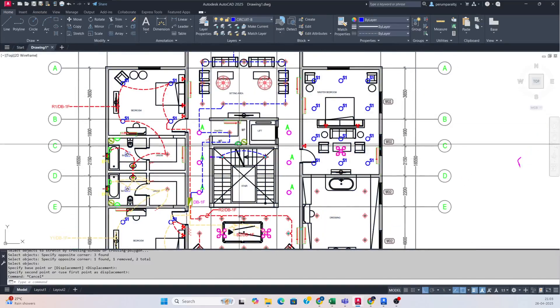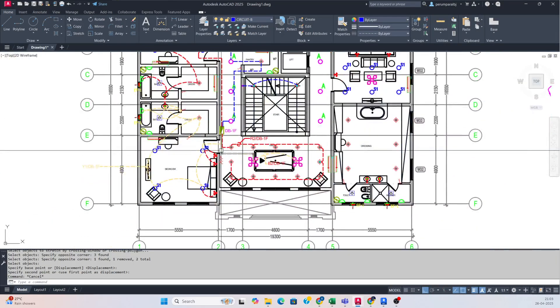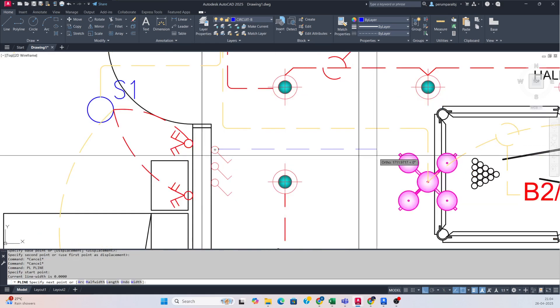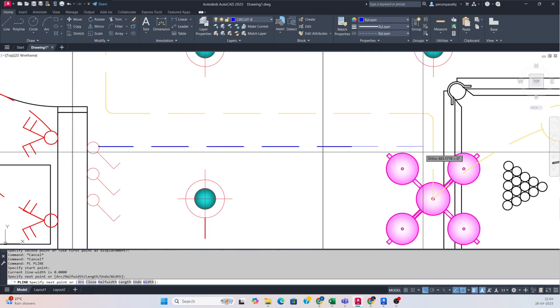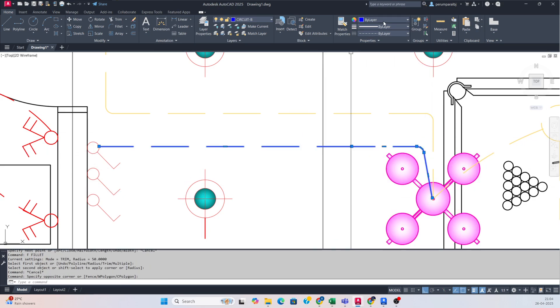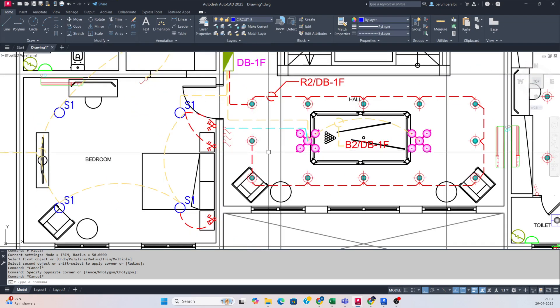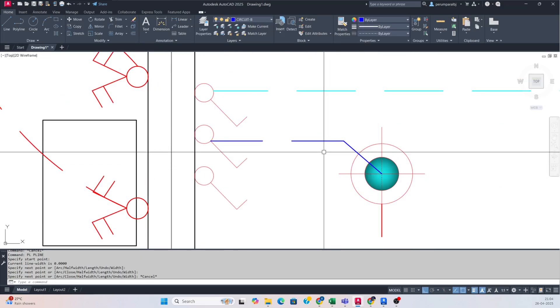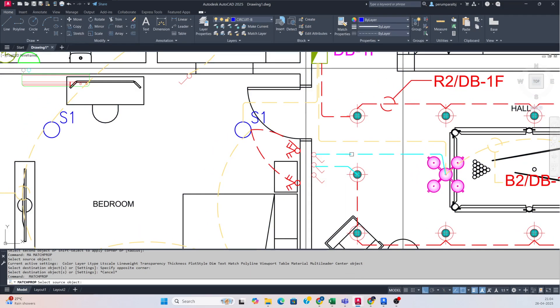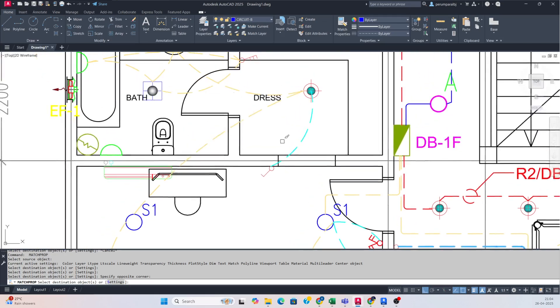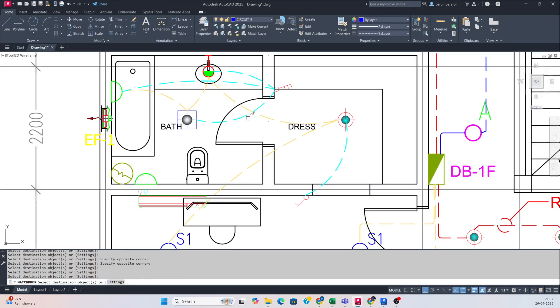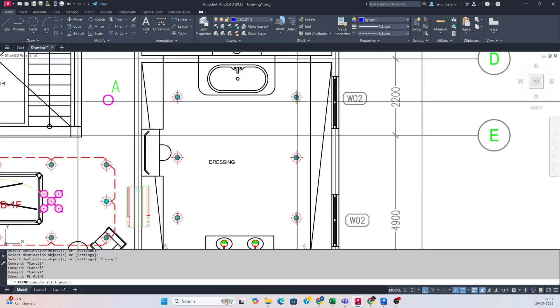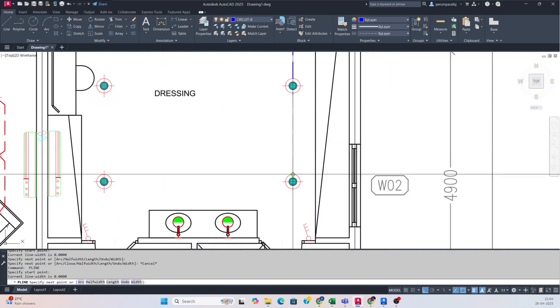The same process applies for all other areas — connect them and reach the DB like this. For switches, check how many switches are here and connect with each light item. You can give another color of wire — that is not an issue. For switches, use a different line type for the wiring so it differentiates between the switch wiring and the circuit wiring. Then go to polyline and give the circuit names like this.